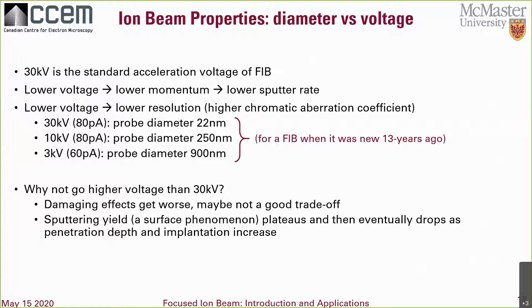Now I'm going to talk about the properties of the ion beam. Let's first talk about what happens to the beam diameter with respect to voltage. 30 kV has become the standard voltage for FIB operation, but FIBs also have a few low voltage settings. At lower voltage, the sputtering yield is lower because there's less momentum. The resolution is also poor because chromatic aberrations are high. In practice, low voltage is mostly used just as a finishing step. If low voltage is bad, why don't we go higher than 30 kV? The damage effects get worse — amorphization, ion implantation go deeper — and the sputtering yield plateaus and then drops as voltage rises.